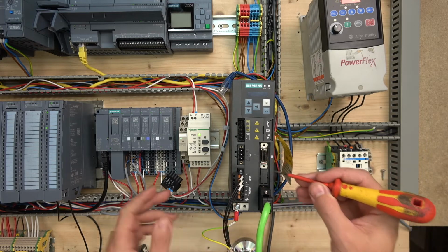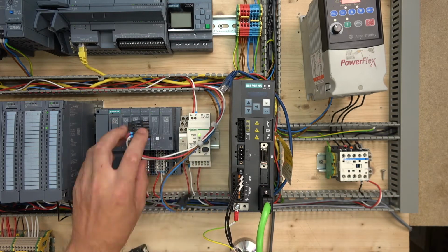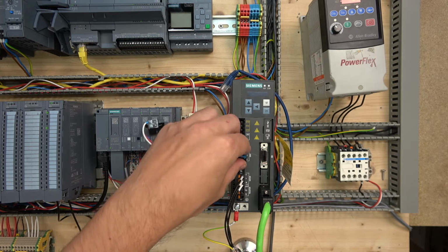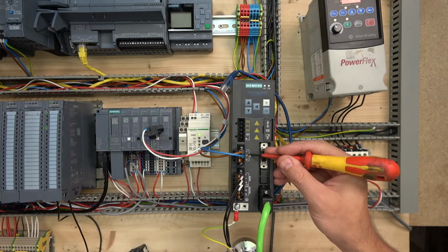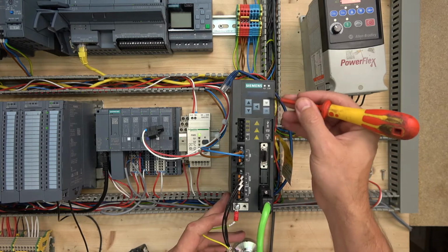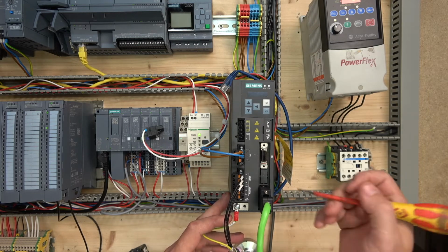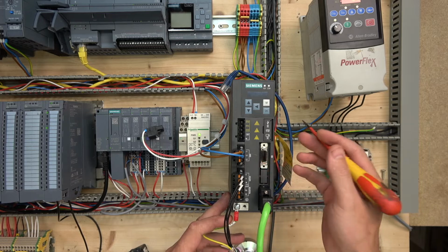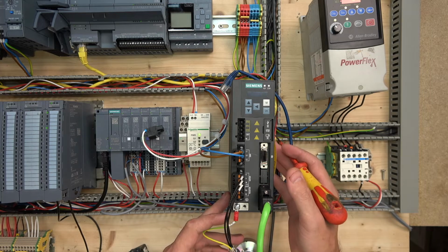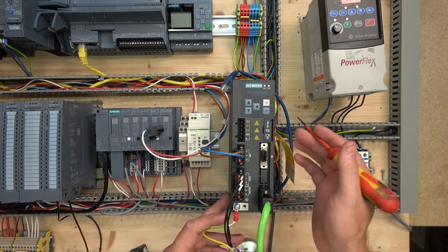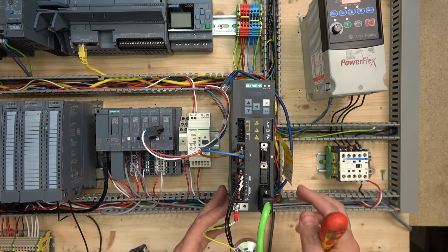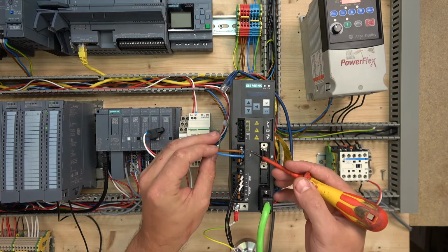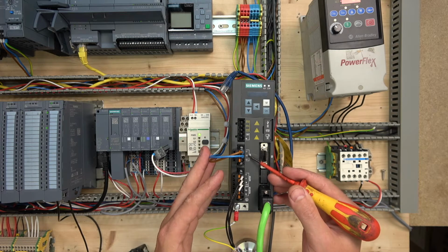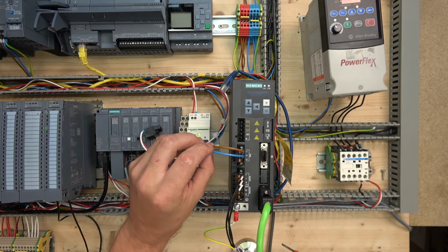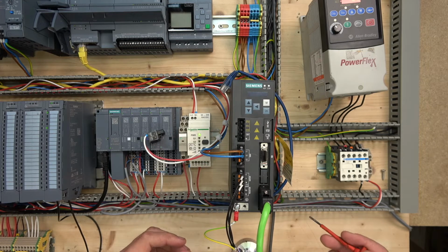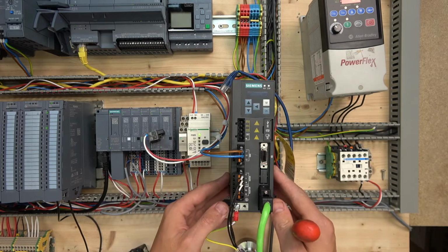From there on, as you can see, we have a plug which is our supply plug: L1, L2, and L3. As you can see, the drive itself does not come alive, because this one is just to run the power part of the actual motor itself. It's not the supply to run the control part of the drive. As you can see, L1 is our plus and L2 is our minus. I know it's a little bit confusing, but it is what it is. That's how it's been set up, so it can be used for both.